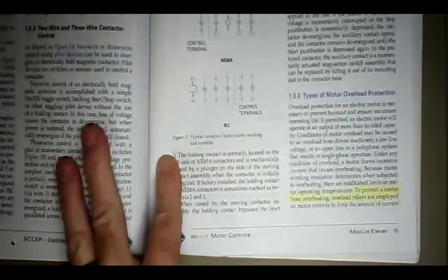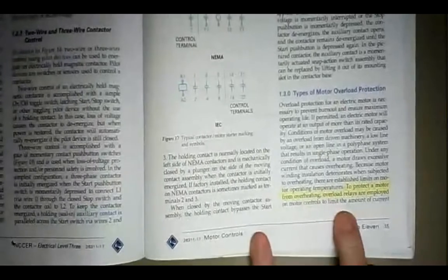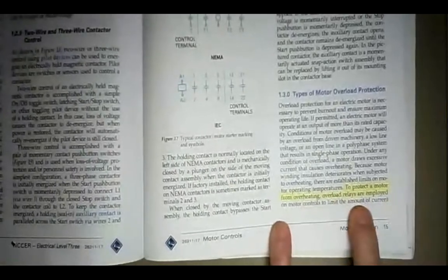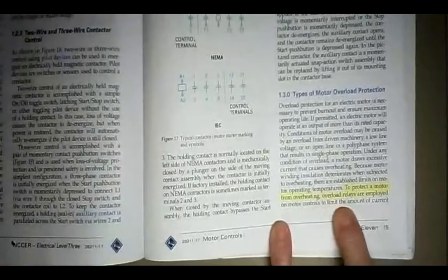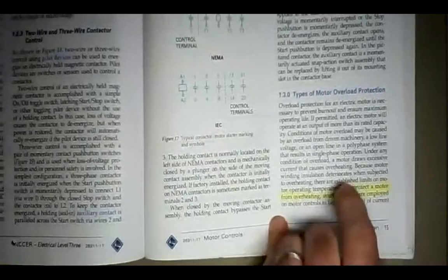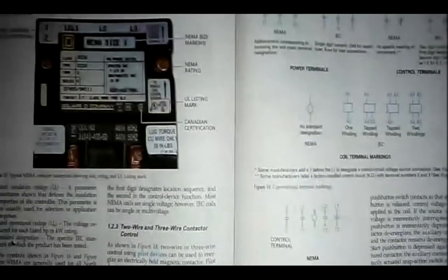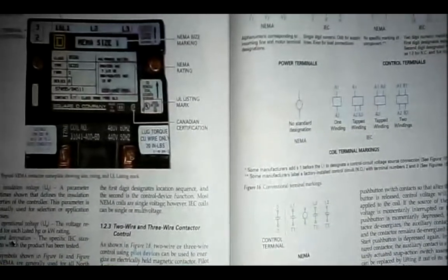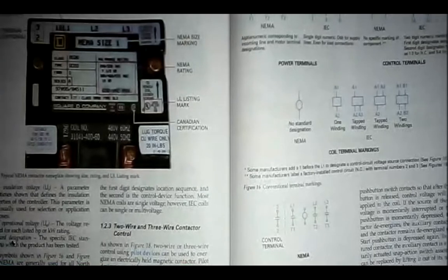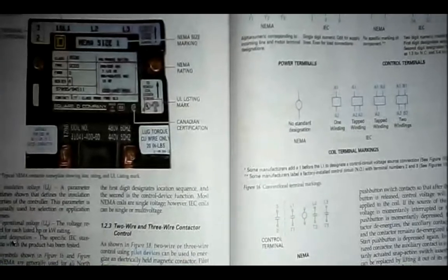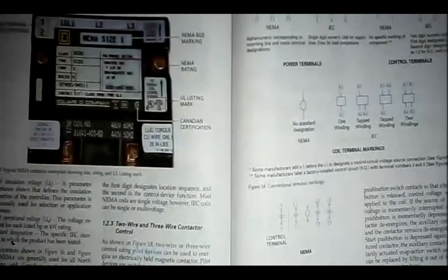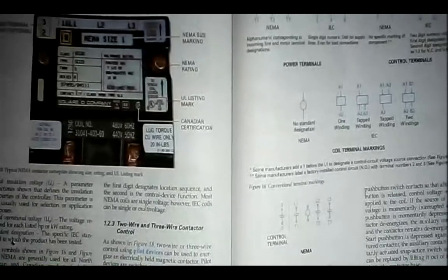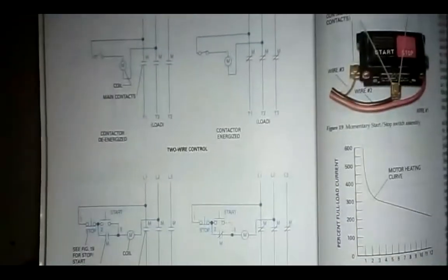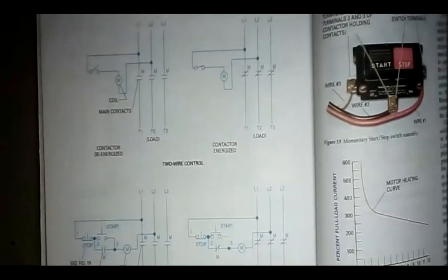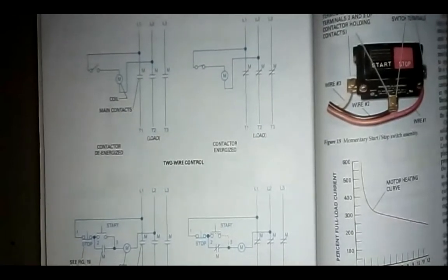And at the very bottom of the right-hand column on page 15, I have this highlight. To protect a motor from overheating, overload relays are employed. The difference between a contactor and a motor starter is a motor starter has to provide overload protection for the motor. You can have a lighting contactor, that's not a motor starter. It has to have some means of protecting the motor from overloads, and then it can be considered a motor controller or motor starter. All right.